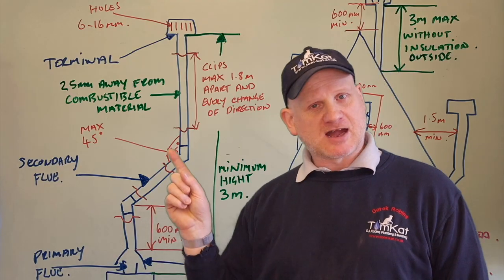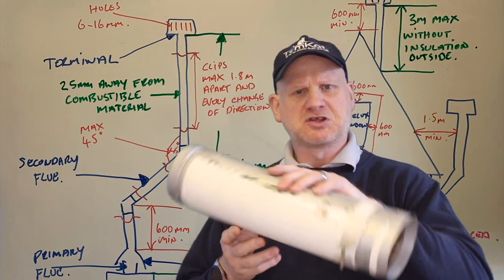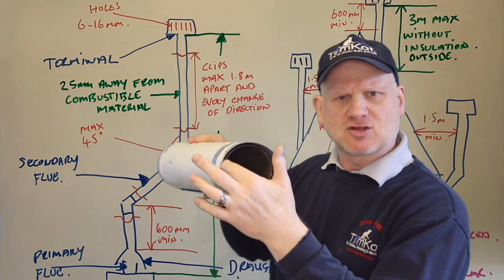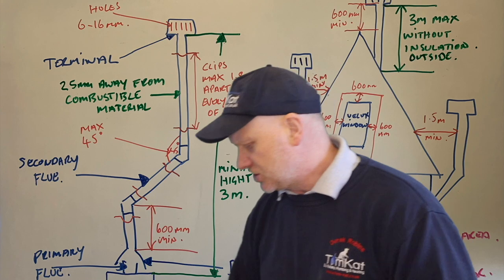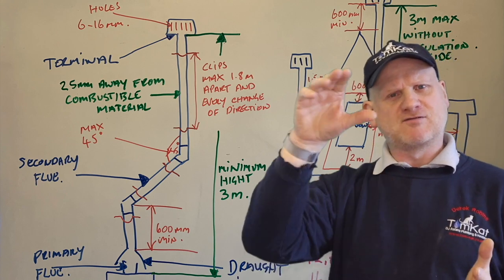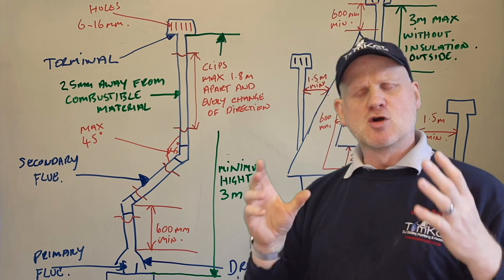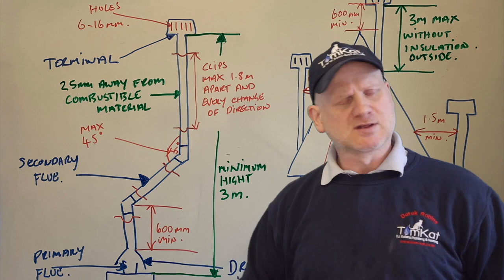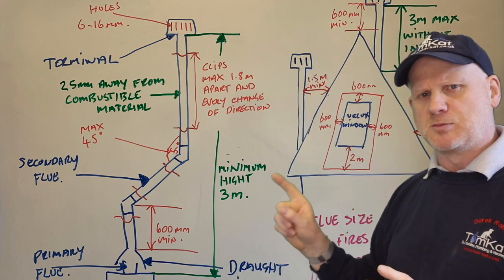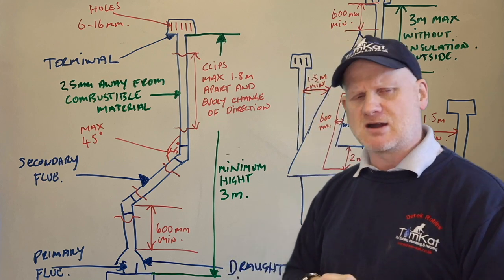Coming off the draft diverter, the next part of the flue system is the secondary flue. The secondary flue is your twin wall flue system. We call it twin wall because the internal part is where the products of combustion go and the external part is an air gap — it stops you getting burnt when you touch it. We have to have a minimum of 600mm from the draft diverter to the first bend. After that, we have flue elbows. The flue elbows cannot have more than 45 degrees of angle. We cannot have horizontal lengths — no 90-degree elbows — because it will cause problems with the pull and condensation.